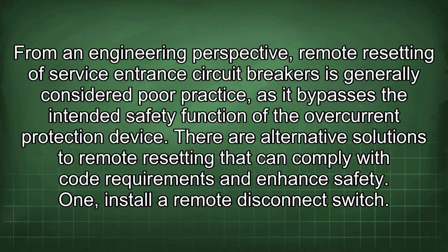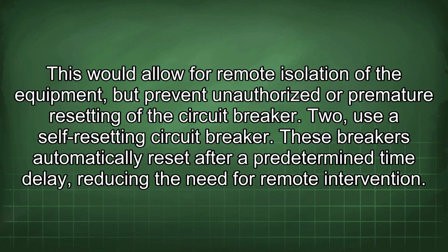From an engineering perspective, remote resetting of service entrance circuit breakers is generally considered poor practice, as it bypasses the intended safety function of the overcurrent protection device. There are alternative solutions to remote resetting that can comply with code requirements and enhance safety. 1. Install a remote disconnect switch. This would allow for remote isolation of the equipment, but prevent unauthorized or premature resetting of the circuit breaker.